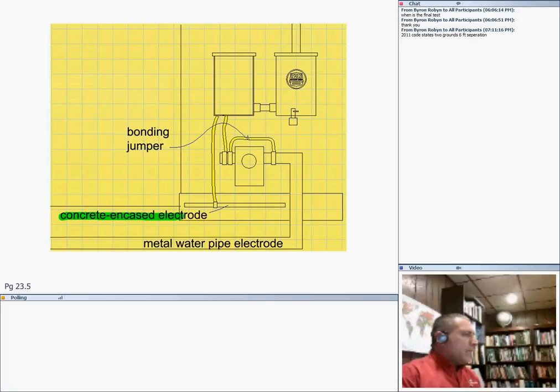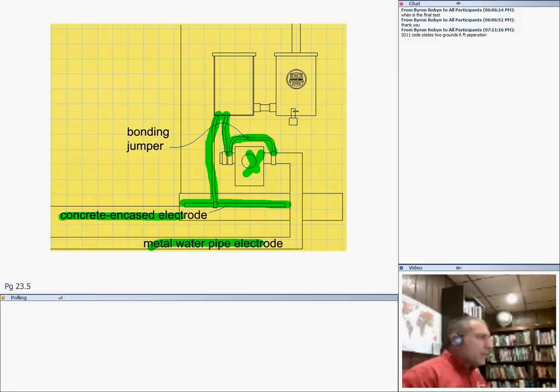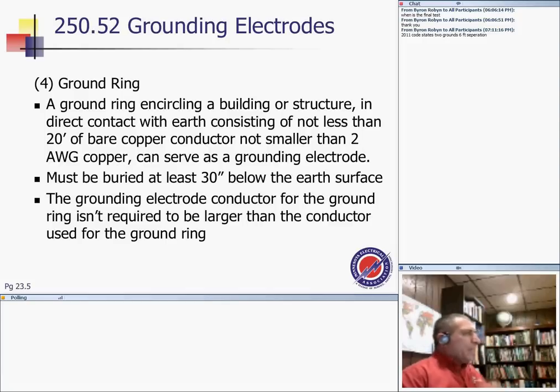With the encased electrode, you guys can see that one here, and you're going all the way to the metal water pipe electrode, and also as long as we jump the meters, for services, you can jump, take the meter out of service, and you still have a grounding electrode system. Any questions, guys, about the grounding electrodes? As you can see, guys, there are so many ways of finding that grounding.